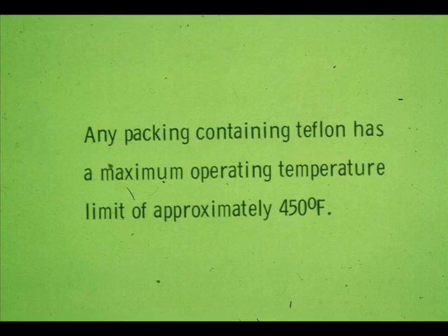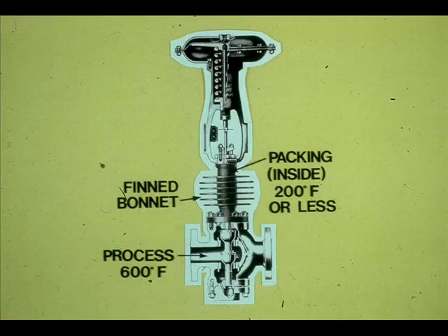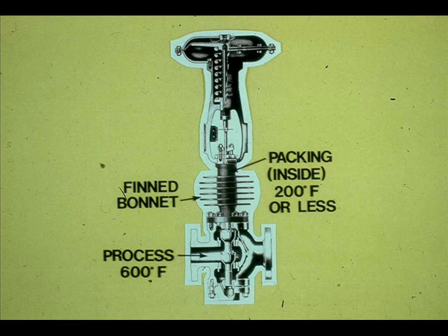Packing materials vary according to services. Teflon impregnated asbestos or graphite is widely used. This type of packing is self-lubricating. Any packing that contains Teflon has a maximum operating temperature limit of approximately 450 degrees Fahrenheit. This is a packing temperature limit, not the process fluid temperature limit. A fin or extension bonnet can be used to cool the packing to below 450 degrees Fahrenheit, even if the process is much hotter.